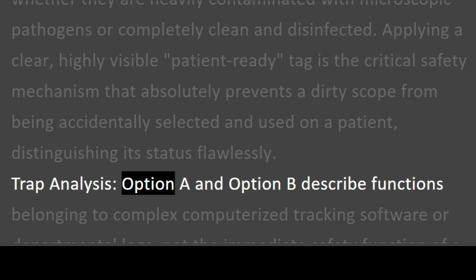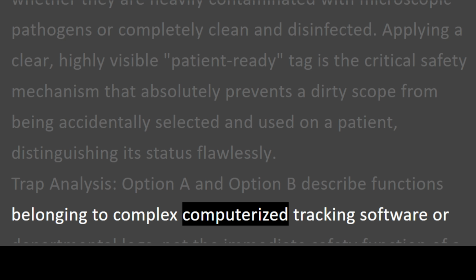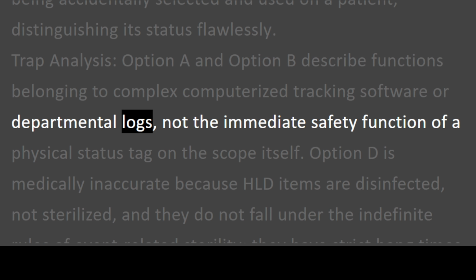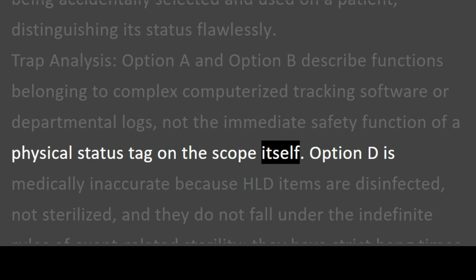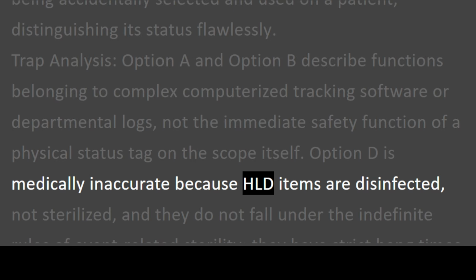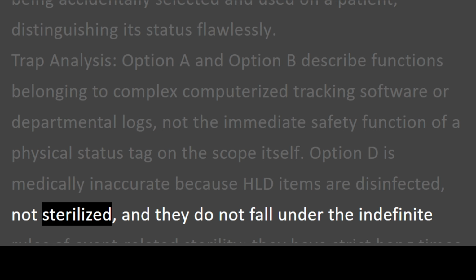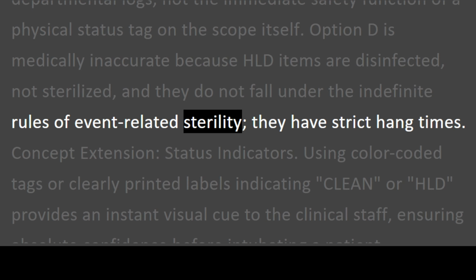Trap analysis. Option A and Option B describe functions belonging to complex computerized tracking software or departmental logs, not the immediate safety function of a physical status tag on the scope itself. Option D is medically inaccurate because HLD items are disinfected, not sterilized, and they do not fall under the indefinite rules of event-related sterility. They have strict hang times.